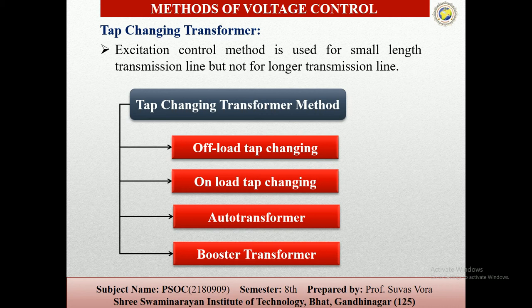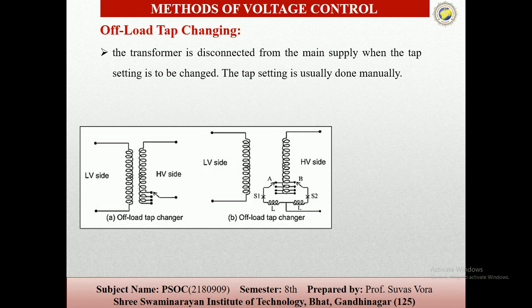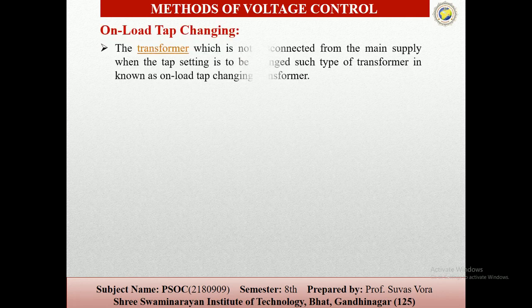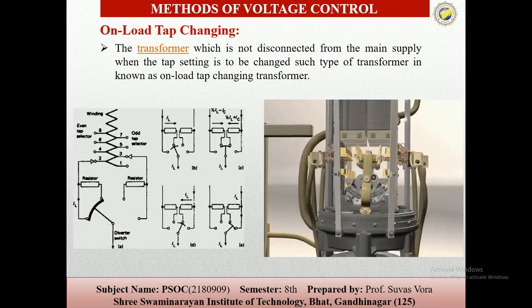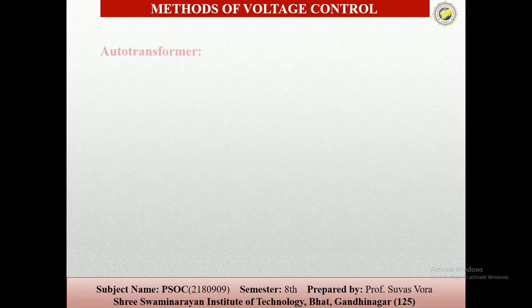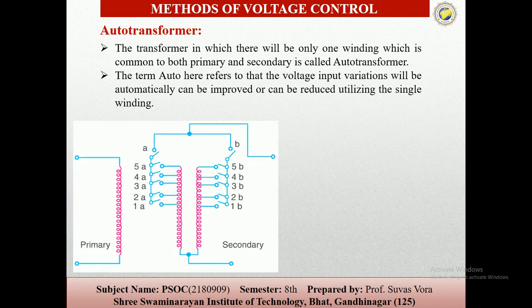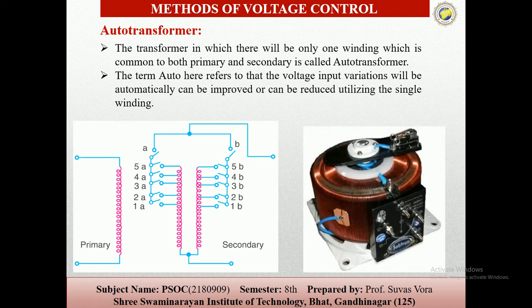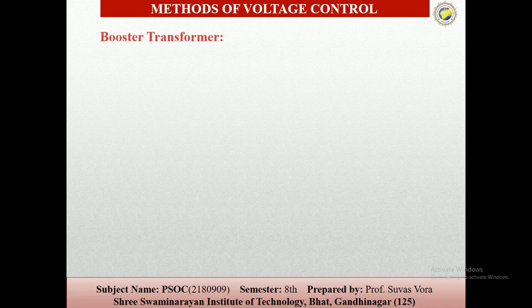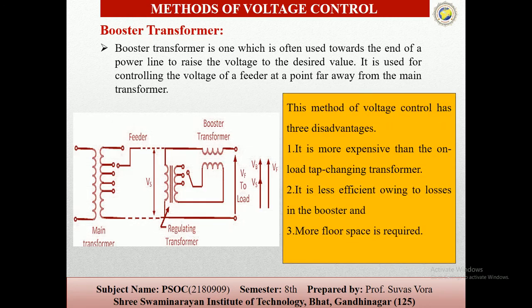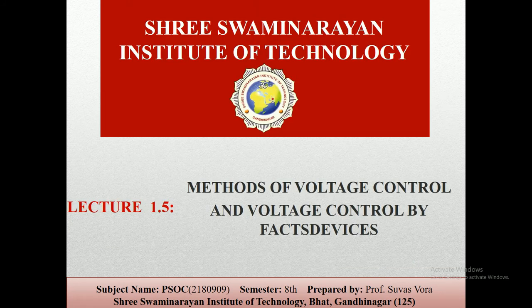An auto transformer has only one winding, and it serves as both primary and secondary. And then the booster transformers. So these are the off-load tap changing. Then the on-load tap changing transformer, you can see that this one is the on-load tap changing transformer. Autotransformers, these are also called the variac, as we know, and booster transformers. So in the last lecture we saw these two methods. Now today's topic is the methods of voltage control and voltage control by the FACTS devices.